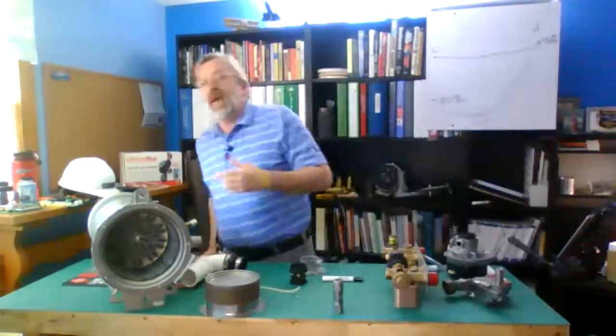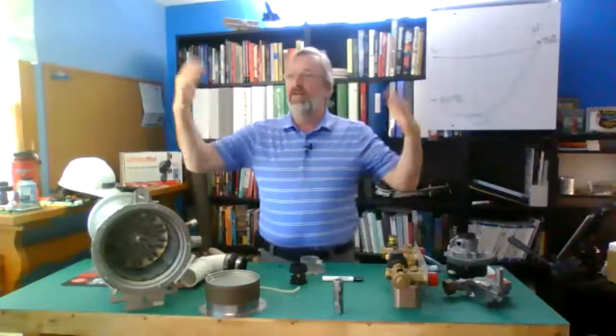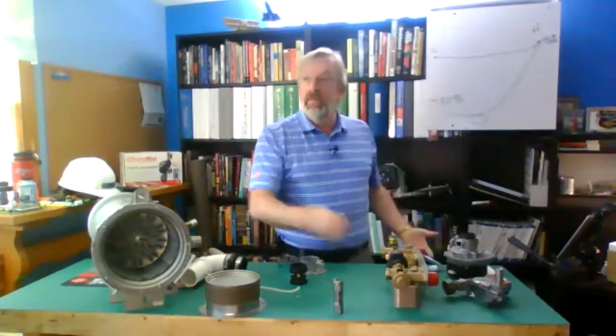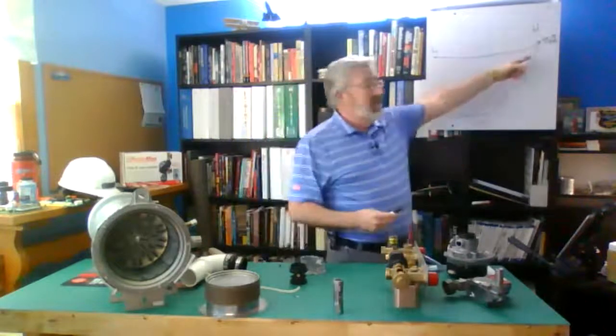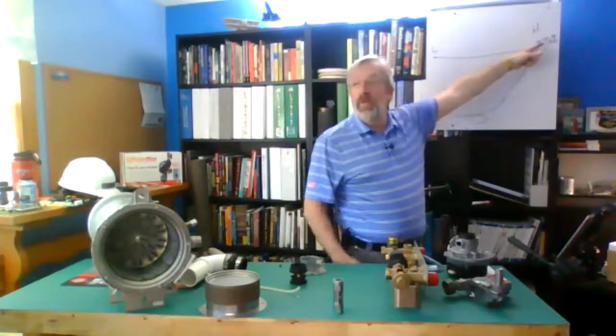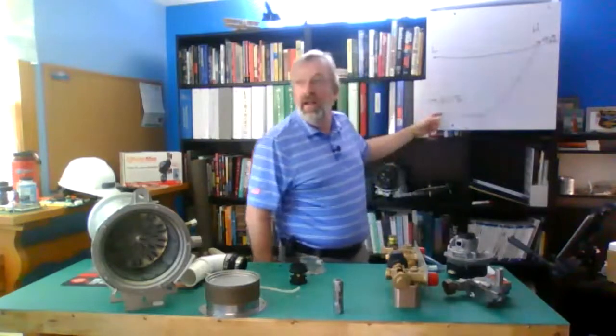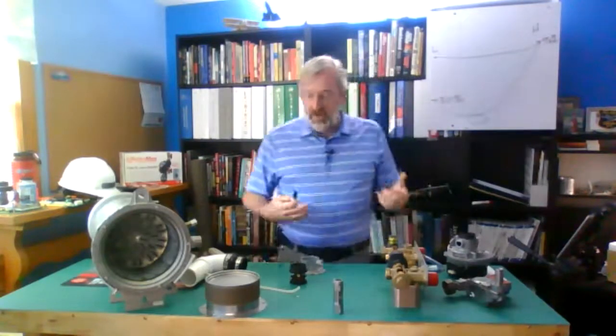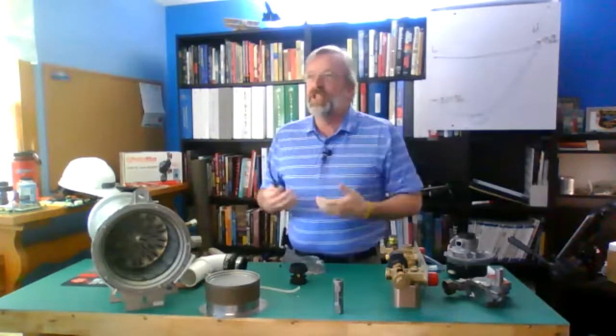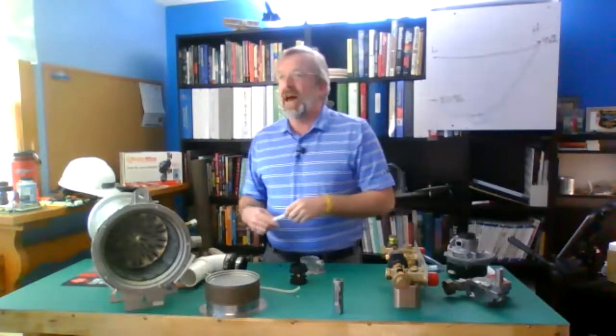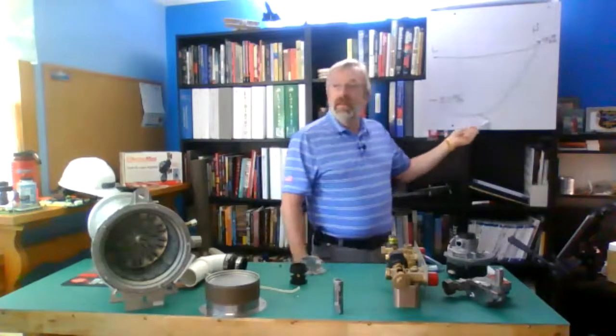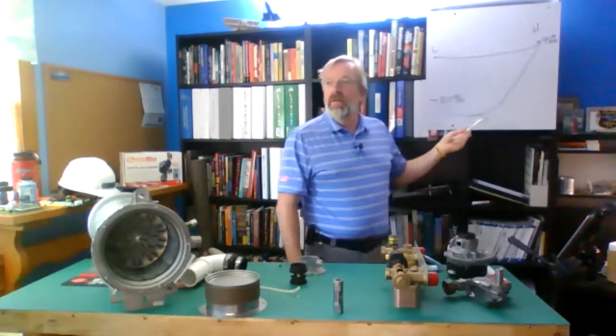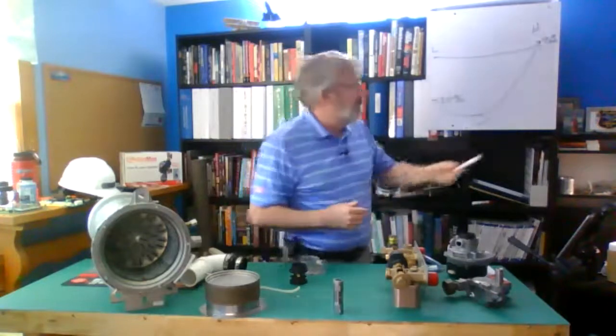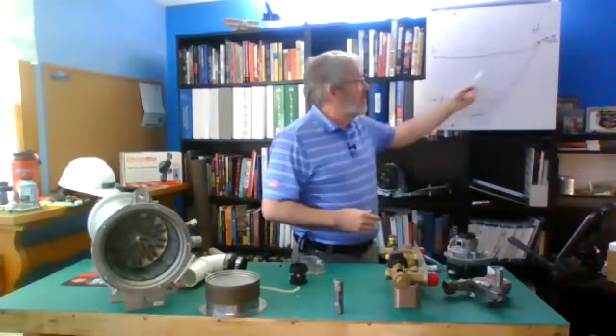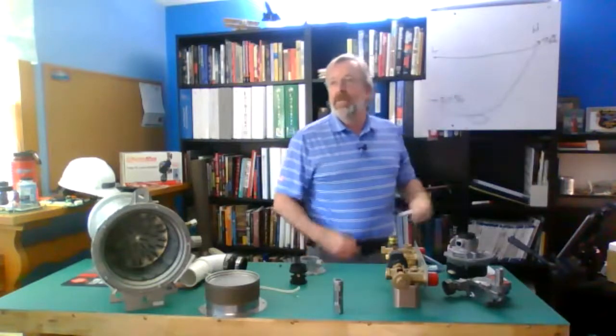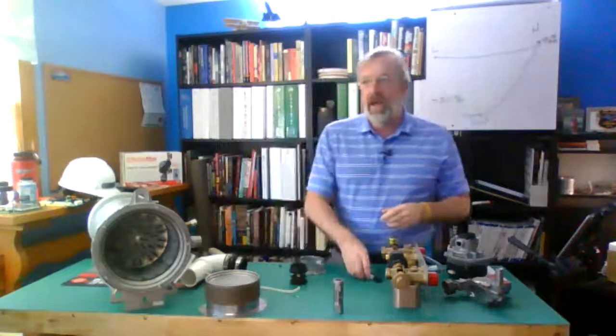And for years, manufacturers never said check high and low fire. So what did we all do? We went out and we're good technicians. We took high fire. We were right where we wanted to be, and we never went over here. And then we had to go back to chase those flame failure ignitions, to chase those noises, to chase all of that. And how do you find that in the middle? Because a lot of times we're not sitting there ramping it up and down. Know that the further apart these are, the better the chance is that happens. So that's why we want to check that in our combustion.